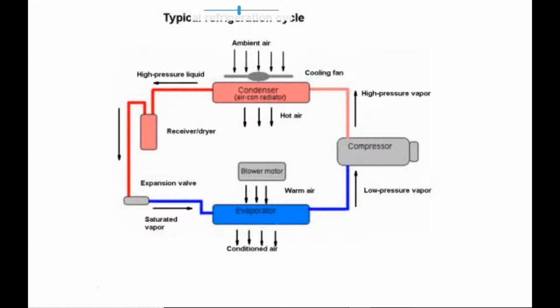So really, there shouldn't be a bit of gas in there. When these do leak, hint hint, if you were to press on the high pressure valve in there, what tends to happen, if it was running well, is you'll get a fine mist, it looks like steam from a kettle.